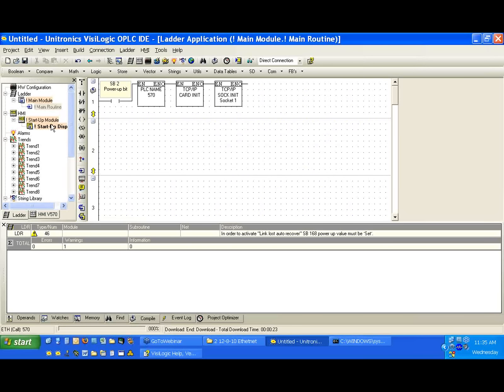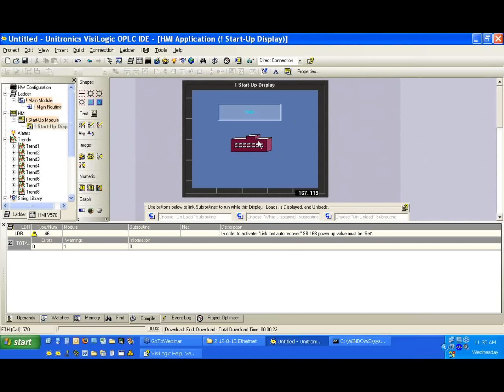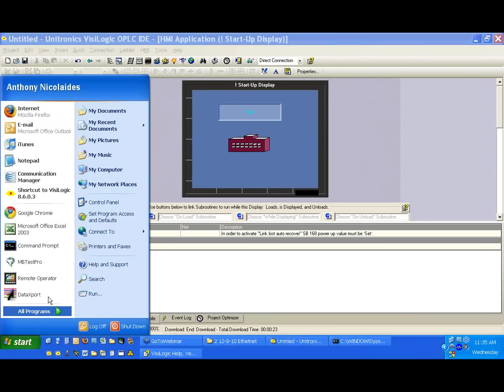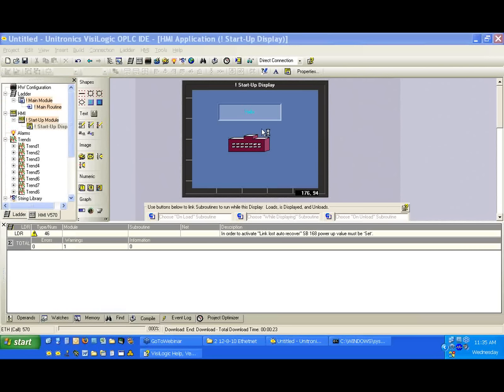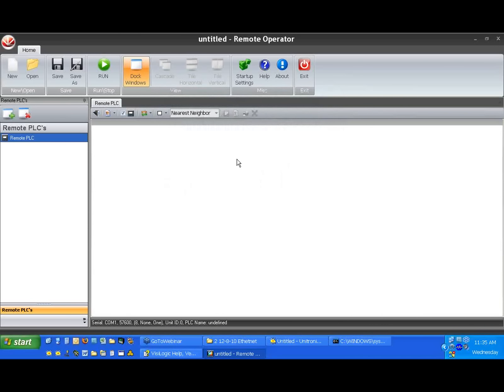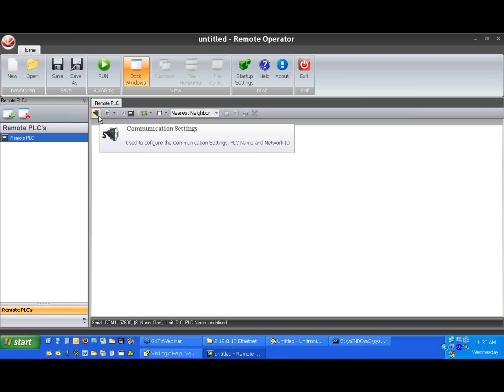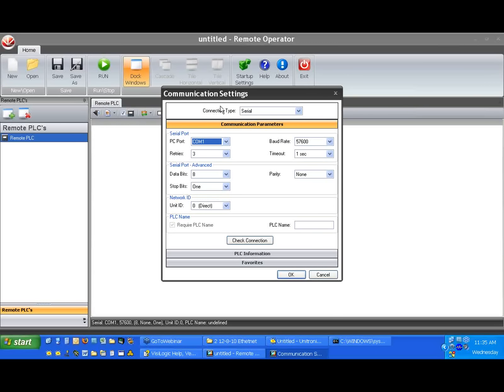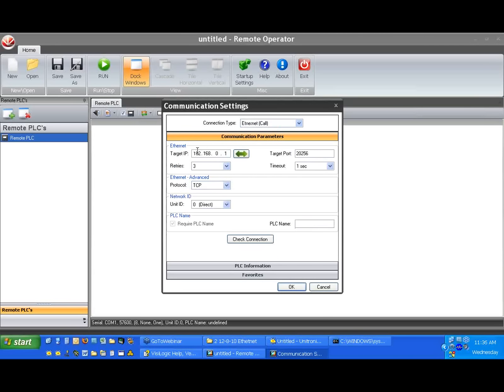Let me just get rid of this. We notice again we have downloaded our program. So I'm going to use another piece of software called Remote Operator. We're going to connect and bring up the screen of the controller. Here's our Remote Operator application — this is available for free download on our download page under Support. First thing we need to do is configure the communication settings, same as we just used in VisiLogic. We'll select Call, put in our IP address — it was 10.2.2.56 — the port is correct, and the PLC name was 570. We can hit the Check button.